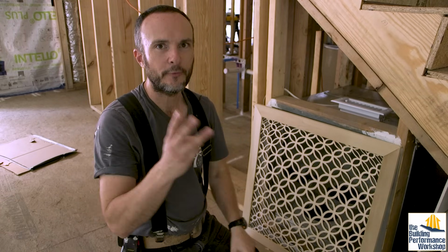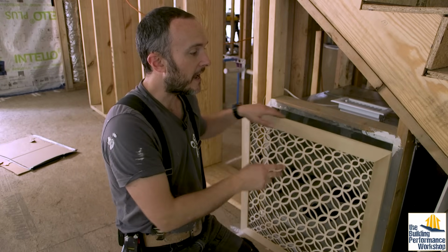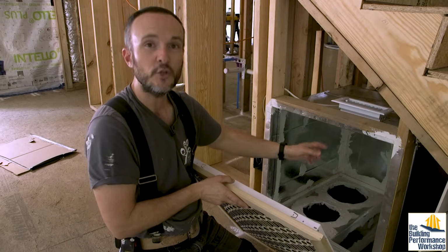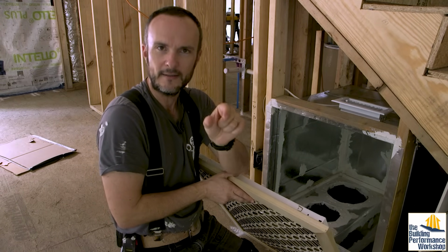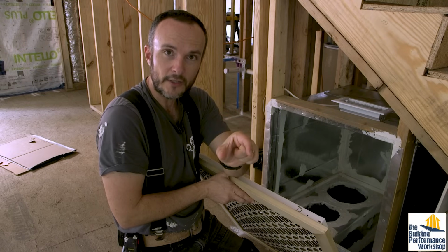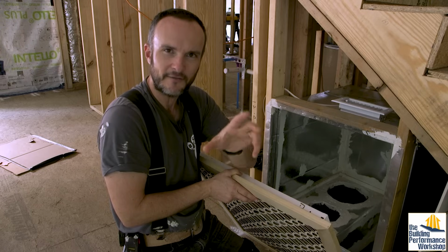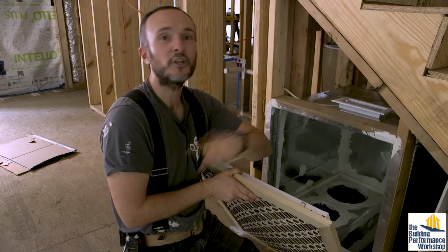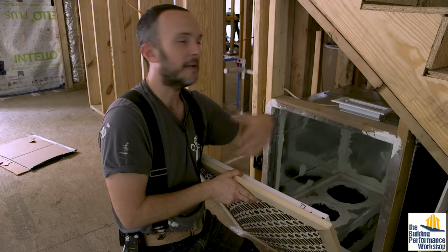This is going to be a 2-inch deep filter. And I can, if I want to, because I've got 3 machines, remember, pulling from this one 2x2 box, upsize this filter to a 4-inch deep filter. When you go from a 1-inch typical to a 2-inch to then a 4-inch, I'm taking the zigzags that go down through it, that's the filter media, and I'm making them much, much bigger, so that the surface area of what is allowed to filter the air becomes much bigger.